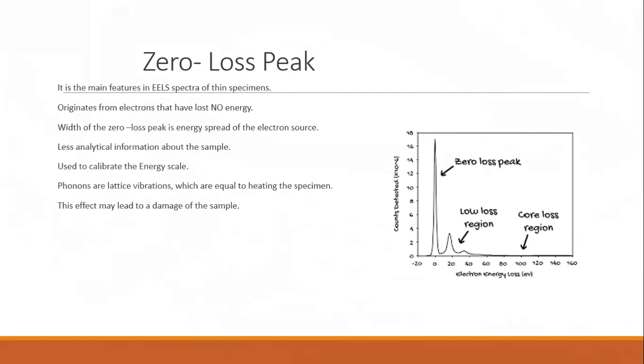Zero loss peak is the main feature in an EELS spectrum of thin specimens. It originates from electrons that have lost no energy. Width of the zero loss peak is the energy spread of the electron source. Less analytical information about the sample. Used to calibrate the energy scale.